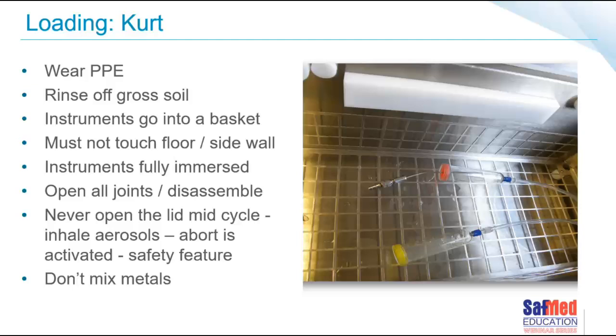I know I've done it before with you, where you're in a hurry or something, and you quickly open the lid. And I know in some of the makes of the model that actually aborts the cycle or something of the sort. That's correct. It has a sensor, and it will trigger that it's been open, and it will abort the cycle. It's the safety feature, 100%. So earlier I mentioned that some of the units won't work without the lid being closed. So that's on the same safety switch. So it's definitely a safety feature.